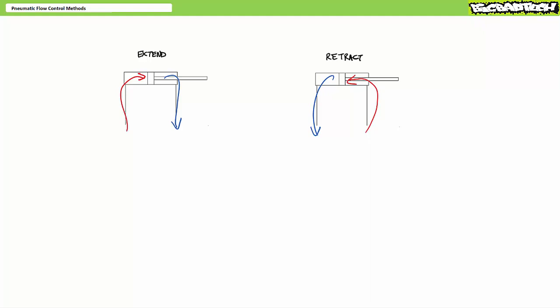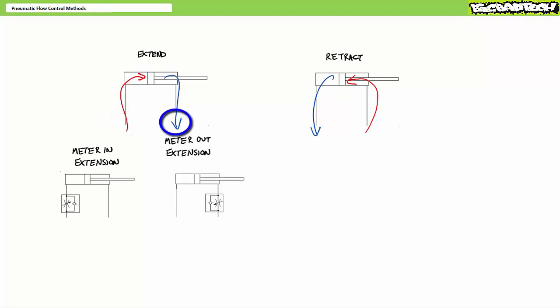This allows us two opportunities to control extension and two opportunities to control retraction. To control extension, we could restrict flow coming into the cap end — the slower the cap end fills up, the slower the cylinder will extend. This is known as meter in extension. Alternatively, we could restrict flow coming out of the rod end — the slower the rod end drains, the slower the cylinder will extend. This is known as meter out extension.